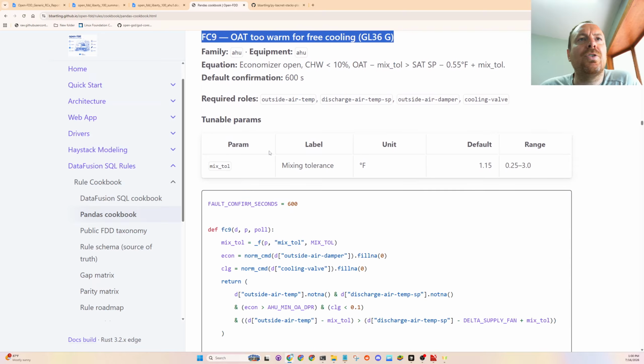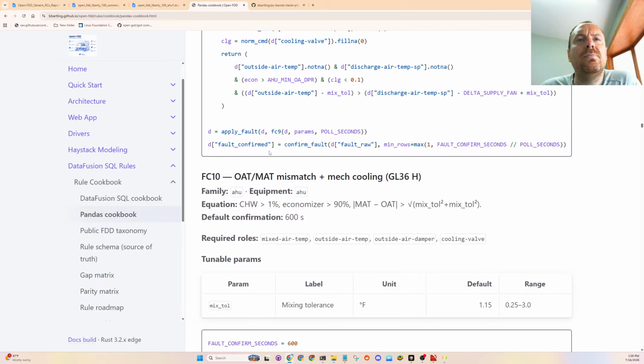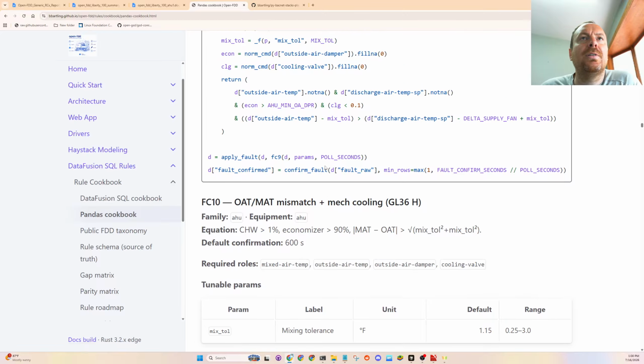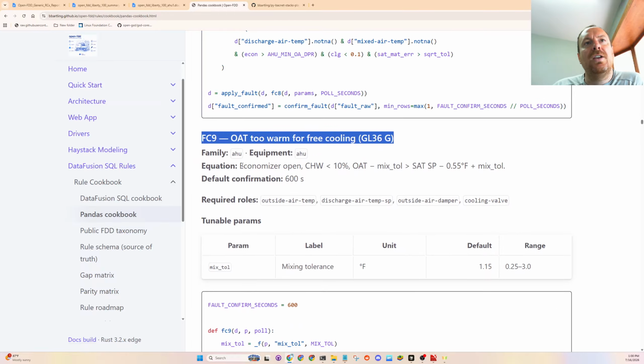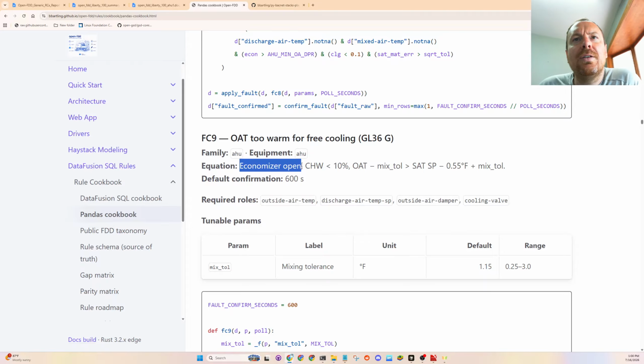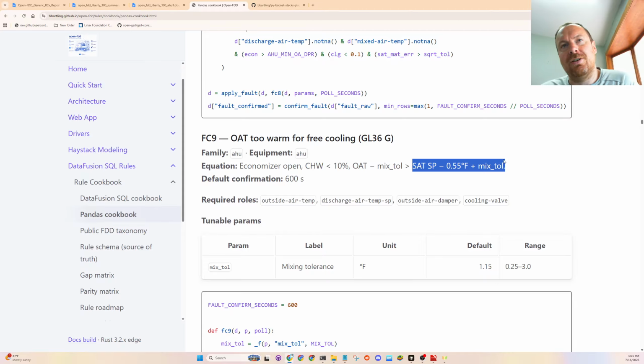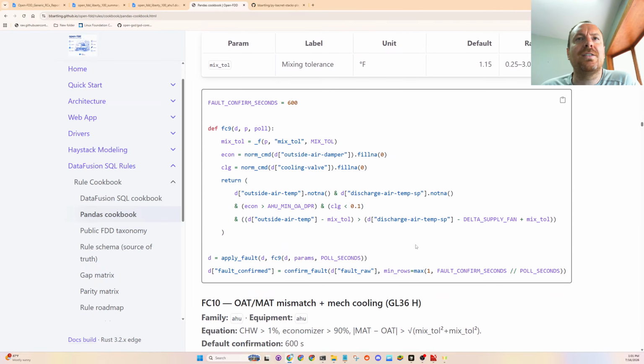Maybe I'll just keep the page open to here. One is for mechanical cooling only. But basically these fault equations look for the outside air dampers open, chilled water less than 10%, and the outside air temperature minus a mixing tolerance being greater than the supply air set point minus a half degree plus a mixing tolerance. So it's all defined by Guideline 36. We'll check it out and see, I think that this passes.